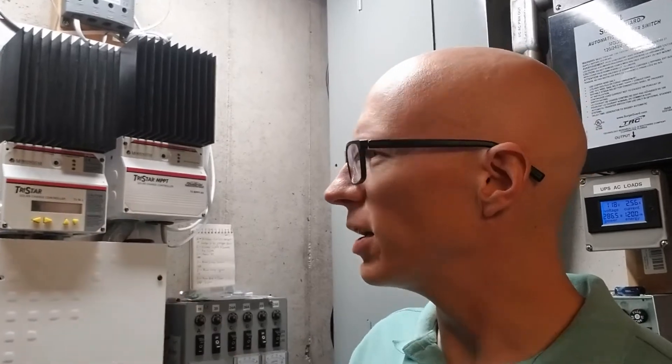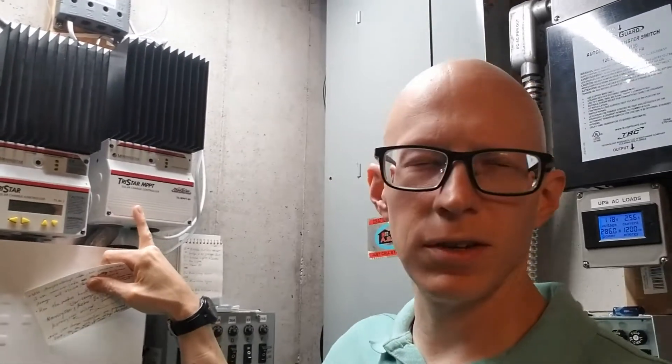It was nice and sunny and this one I got all hooked in and running, communicating. And this one just dropped off and stopped charging. What happened is this one had a max voltage setting on it that was much lower than this one, and so the whole system stopped pulling in solar power.